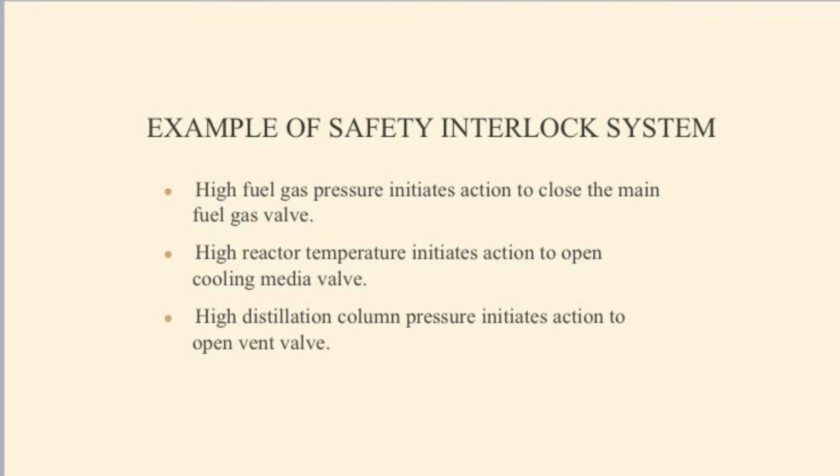Examples of safety interlock system. First, high fuel gas pressure initiates action to close the main fuel gas valve. Second, high reactor temperature initiates action to open the cooling media valve. And third, high distillation column pressure initiates action to open the vent valve.